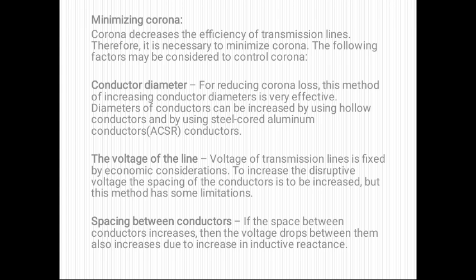Next is the voltage of the line. Voltage of a transmission line is fixed by economic consideration. So to increase the disruptive voltage, the spacing of conductors is to be increased, but this method has some limitations. Next is spacing between the conductors. If the space between conductors increases, then the voltage drop between them also increases due to increase in inductive reactance.